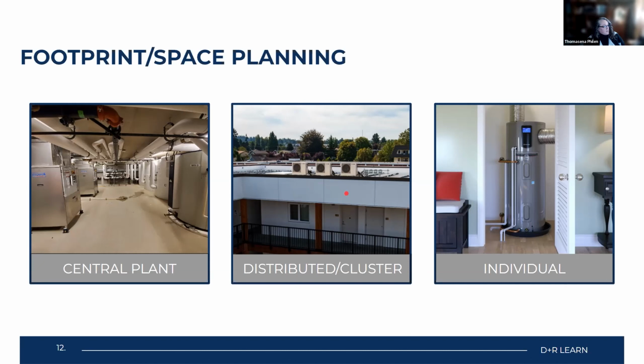This is a distributed cluster. These are small inverter-driven CO2 heat pumps, and they are up on the roof, and they are connected to a storage tank just below in the machine room for that floor. Each one of these units serves 3 to 4 dwellings, best word for that. And so there are a total of 13 units on top of this roof at Hopeworks Station, and they serve the hot water needs for the entire 56 units that are there in the building.